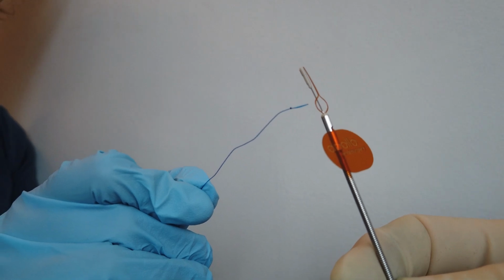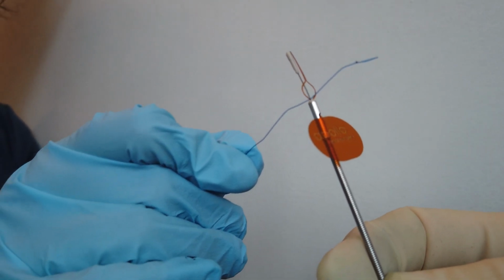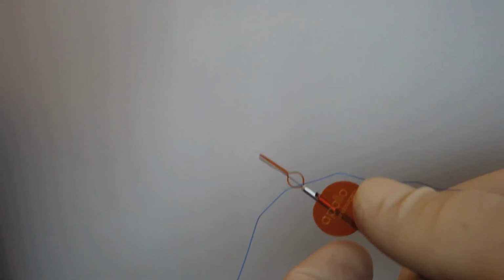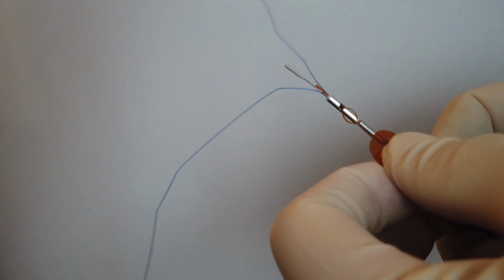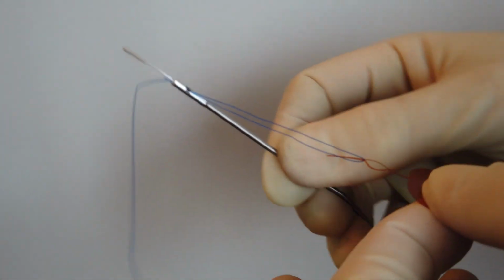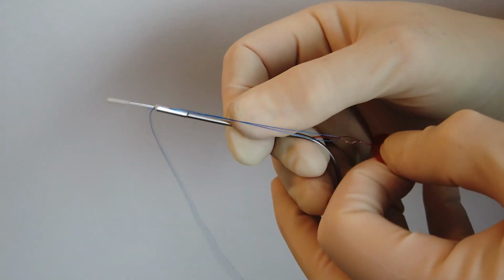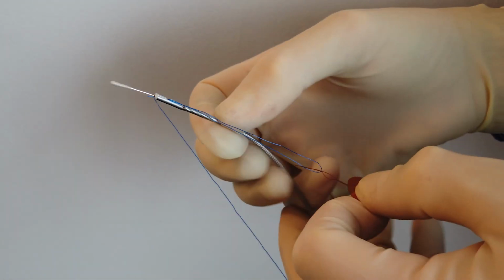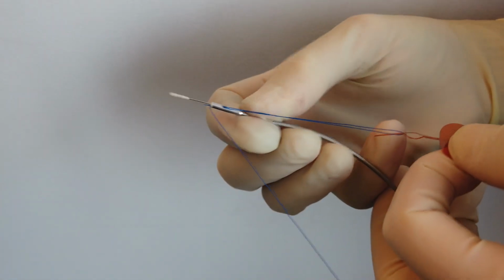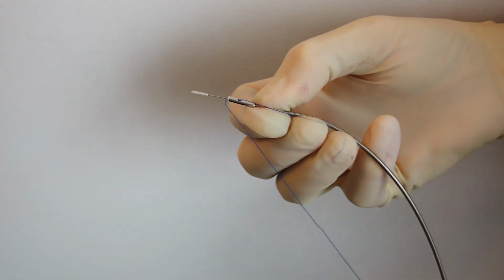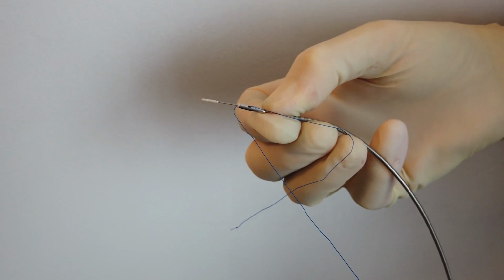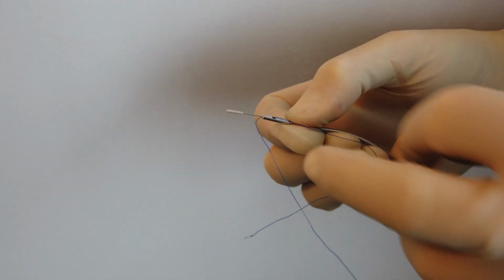The cinch that secures the closure is mounted on a separate delivery tool. Prior to cinch insertion, the external end of the suture must be passed through the thin orange plastic threader loop that sits just proximal to the plastic cinch. The flat tab of the orange threader is then grasped and tugged, which pulls the suture through the tip of the delivery device. Next, the end of the suture must be held steady while the cinch device is passed through the scope into the colon.